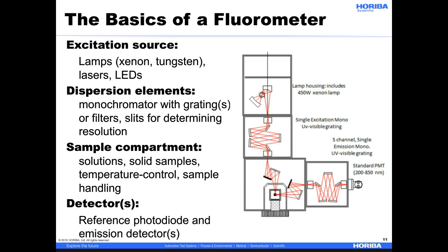Now let's go through the basic components of a fluorometer. First, we have the excitation source — typically a xenon lamp for a steady-state fluorometer. The broad output of the xenon lamp in the UV-visible range makes it perfect for use in steady-state fluorometers. Other systems may use lasers, laser diodes, or LEDs, especially for fluorescence lifetime measurements. Next, we use monochromators or filters to select the wavelength and bandpass of light that gets to the sample. The monochromator may include a diffraction grating, where the angle of the grating determines the wavelength of light selectively used. The excitation light then goes into the sample compartment, where you can have a variety of sample holders and handling options including stirring, temperature control, solid or solution holders, and even remote fiber coupling. The sample compartment contains the first of our detectors — the reference photodiode — which measures the lamp output so that any measurement by the emission detector can be corrected for changes in lamp intensity.